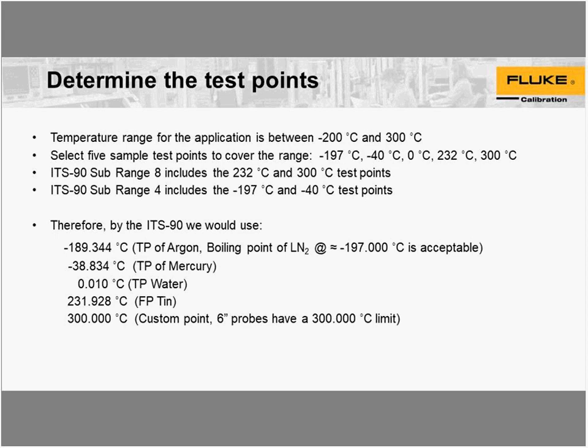The freeze point of mercury is minus 38.834. Triple point of water is 0.010. Tin is 231.928 degrees, and then the 300 degree is a custom point. That happens to be the maximum limit of a 6-inch probe, just because when putting it at a higher temperature, you stand the risk of overheating the transition handle.